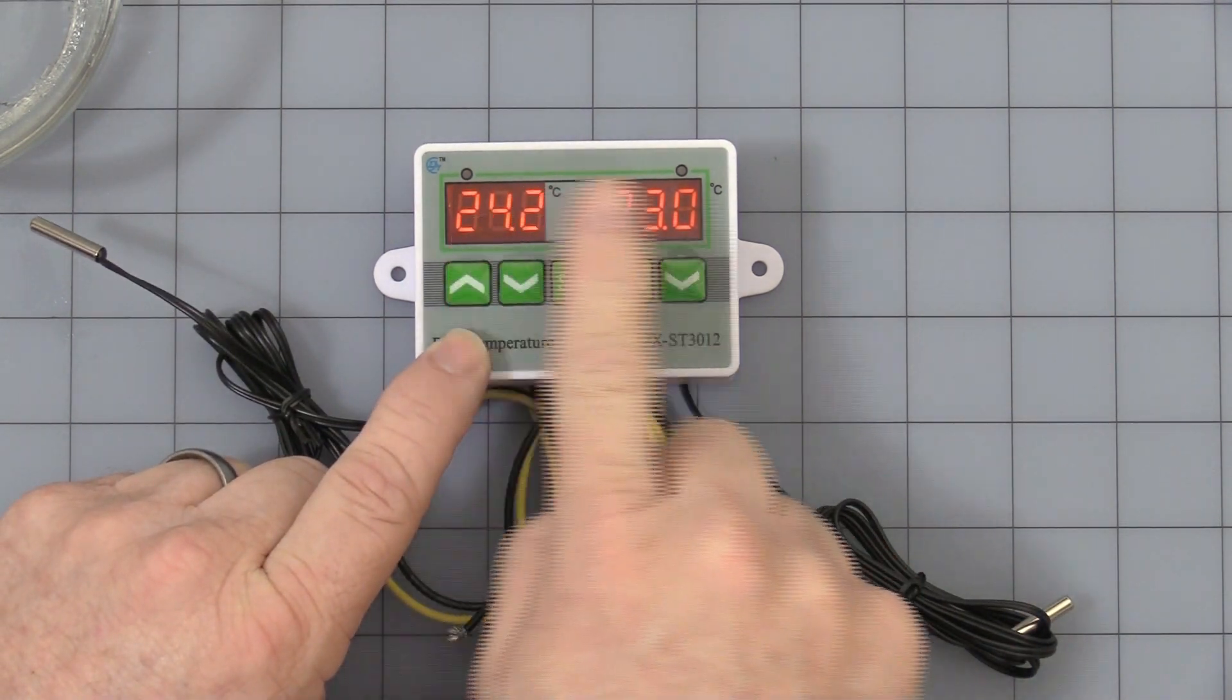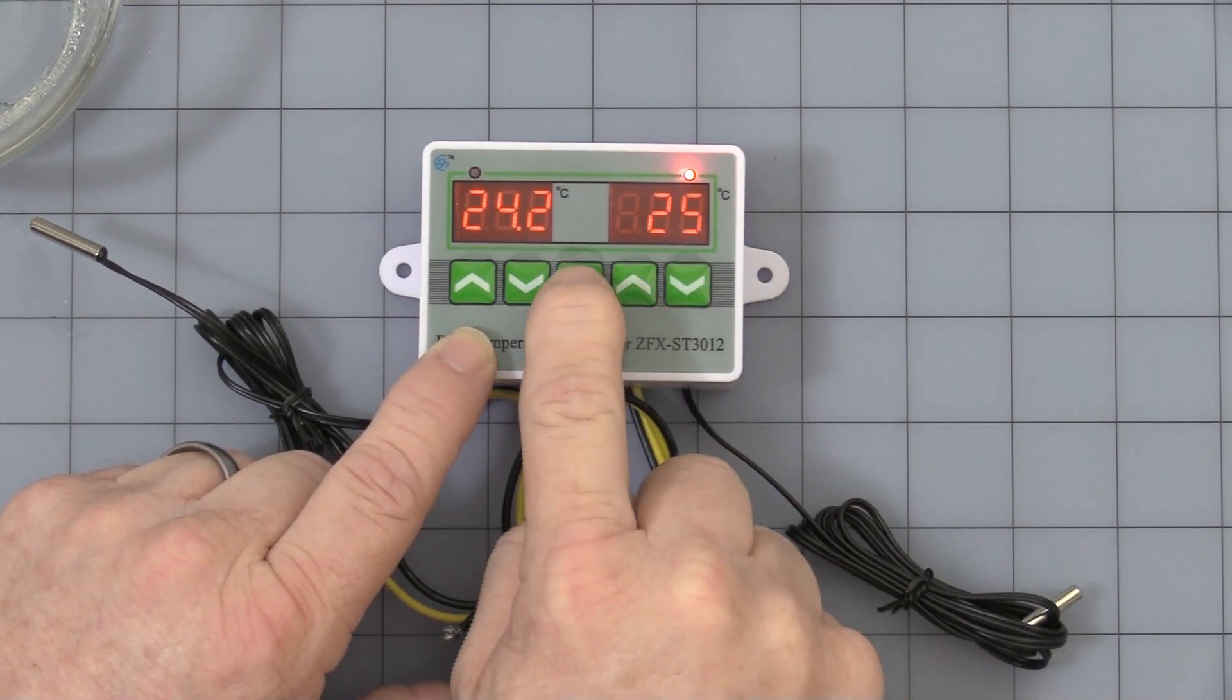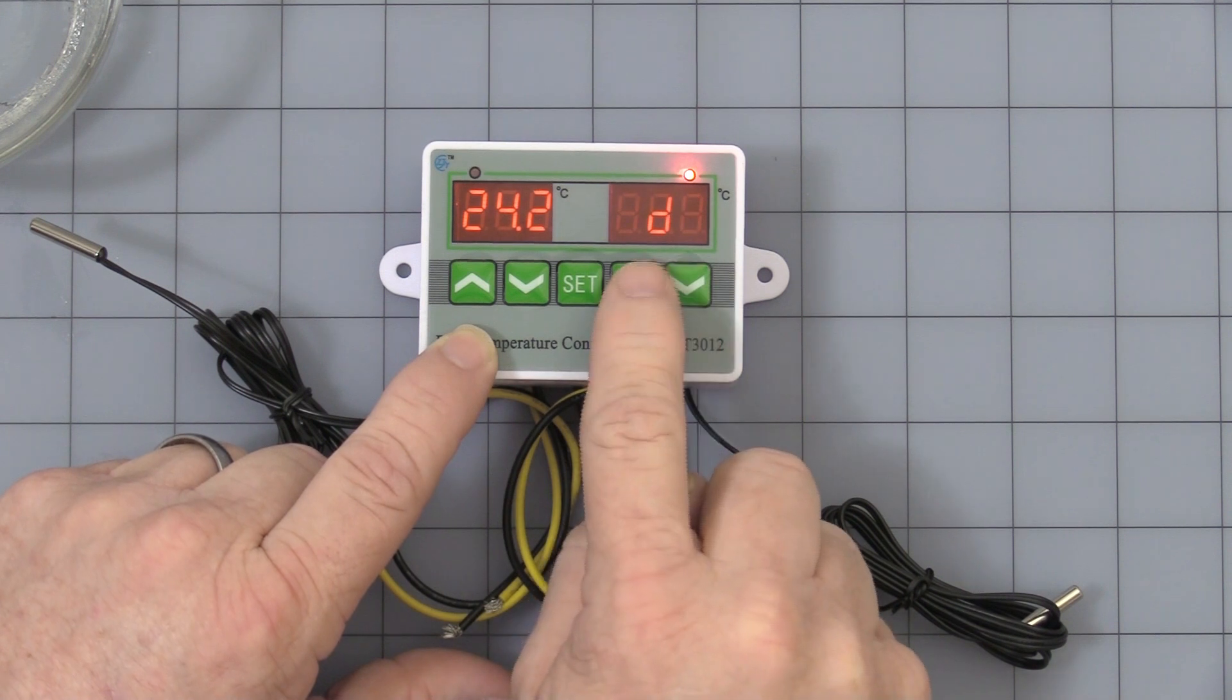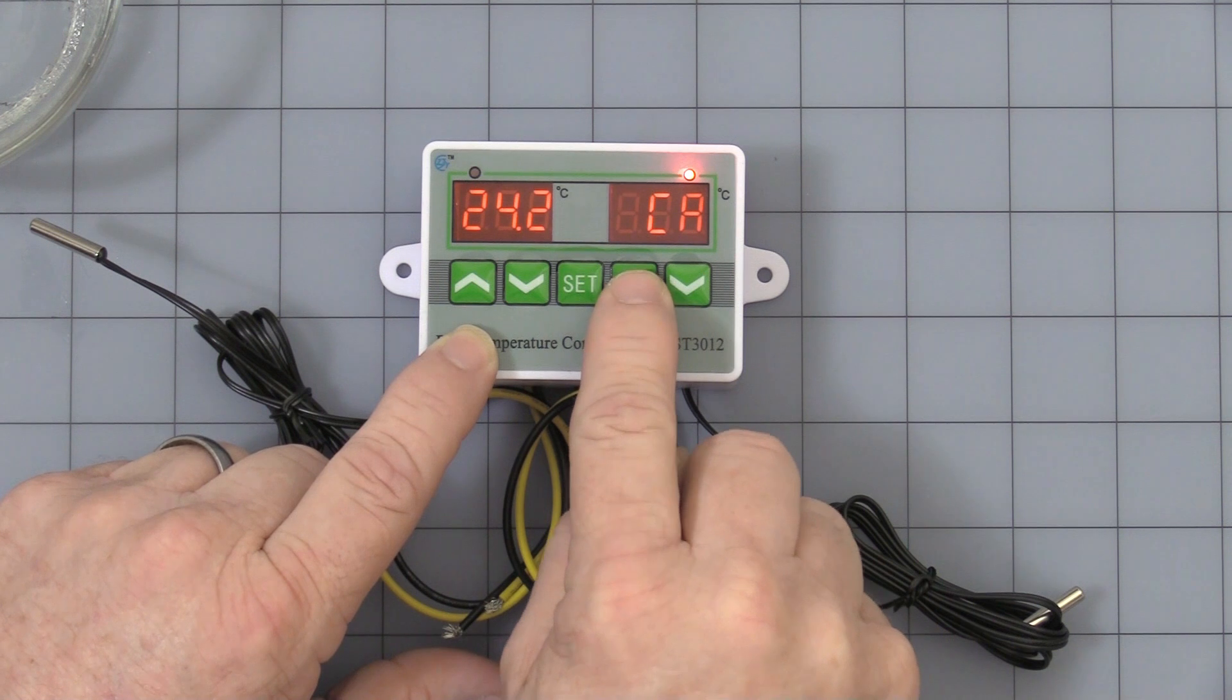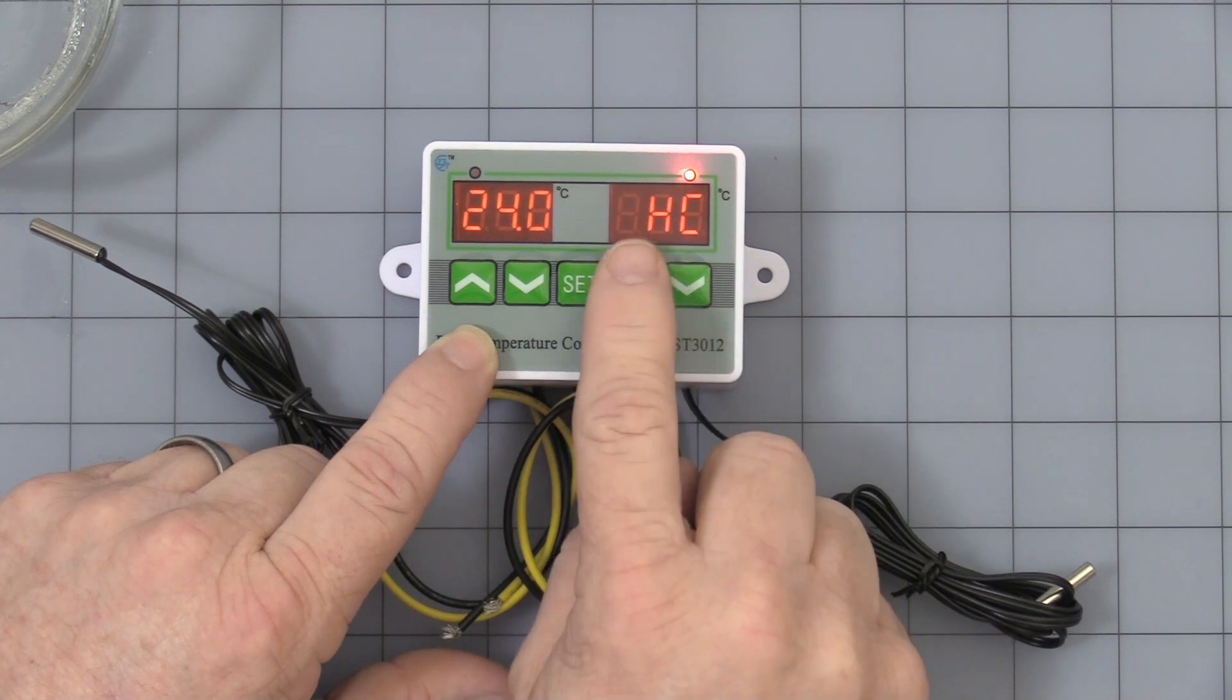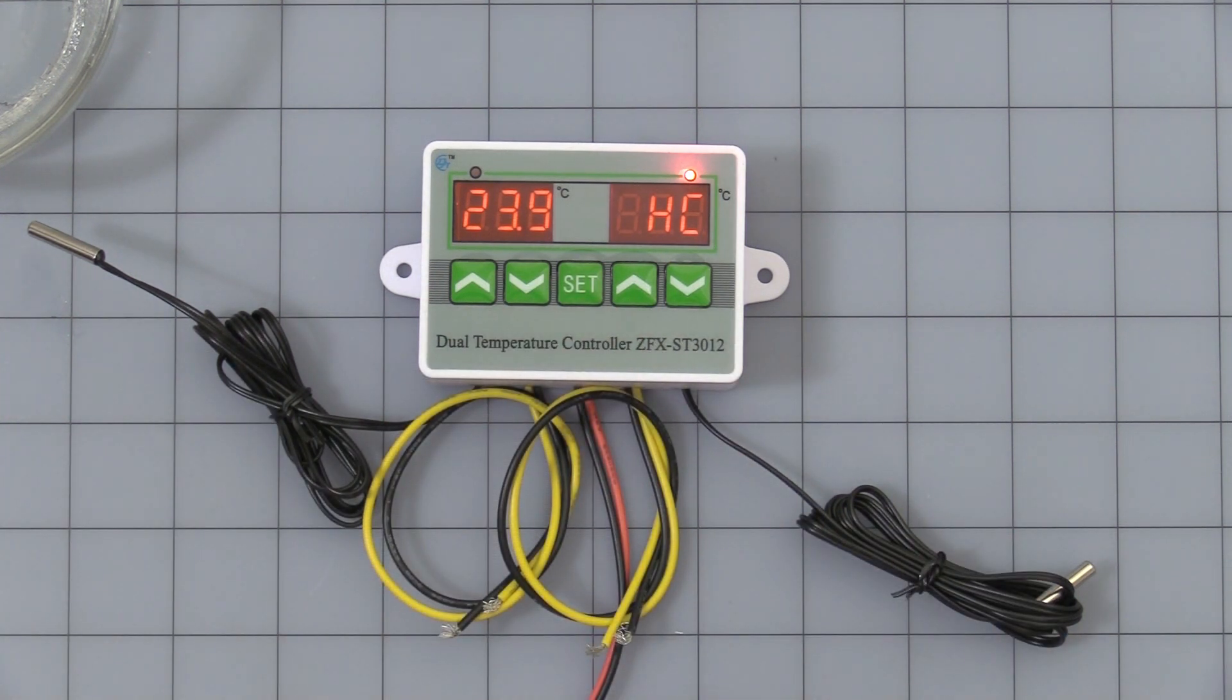Same exact thing works for this side, works for this side. Press it once, it's flashing. Now when it's flashing on this side, you press and hold, and you have all the same programming. There's hysteresis, there's a low temperature alarm, high temperature alarm, calibration, the same power on delay, and back over to heating or cooling. This is factory set to cooling also. When you leave it alone, it goes back to normal operation.